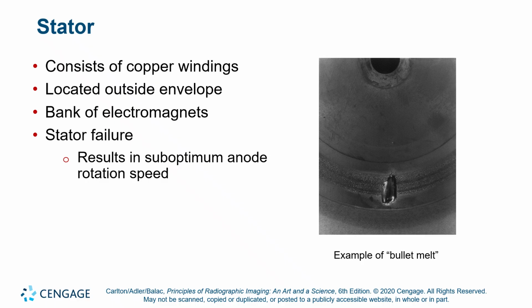Stator failure. If the stator fails to create a rotating magnetic field, because motors do burn up, then you won't create rotational motion, and then you get bullet melt, or basically pit melting. Okay. If you've ever done any machining or welding and you've worked with a cutting torch, you might recognize that sore on the anode. Basically, you turned your X-ray machine into a cutting torch by having a non-rotating anode when it's intended to rotate.